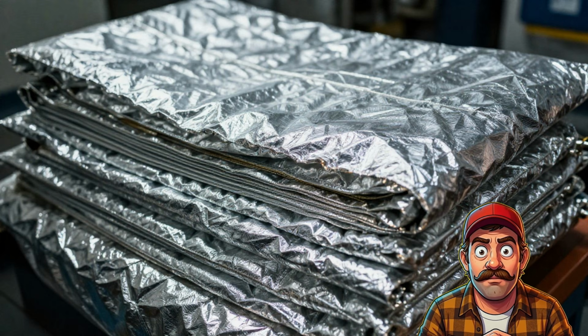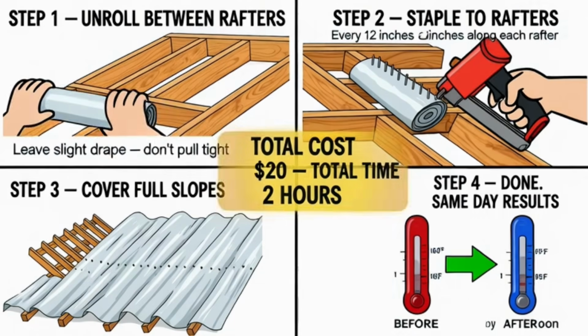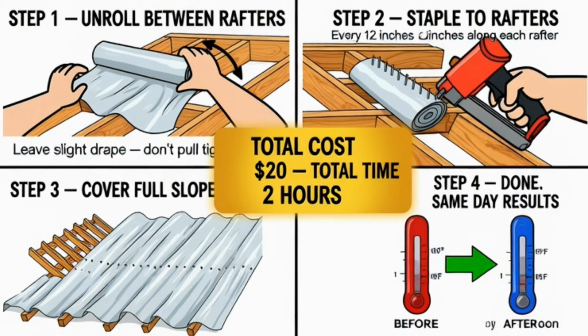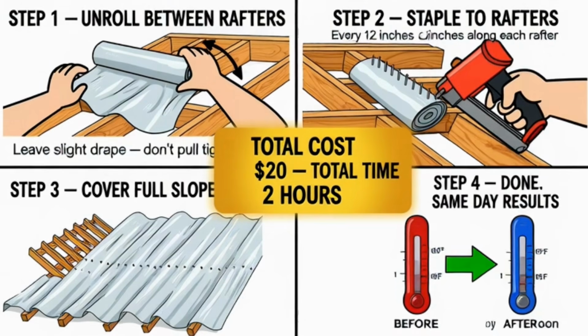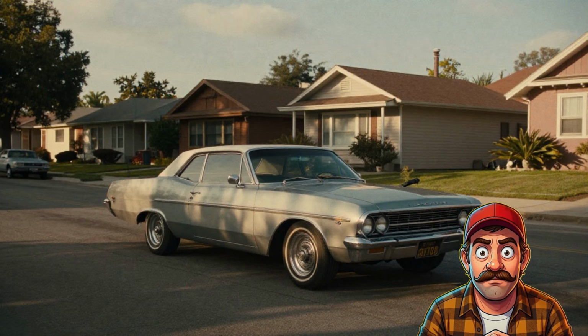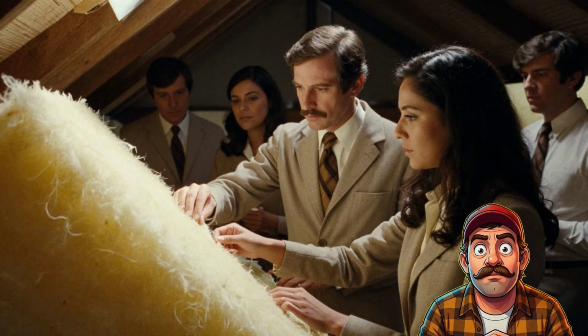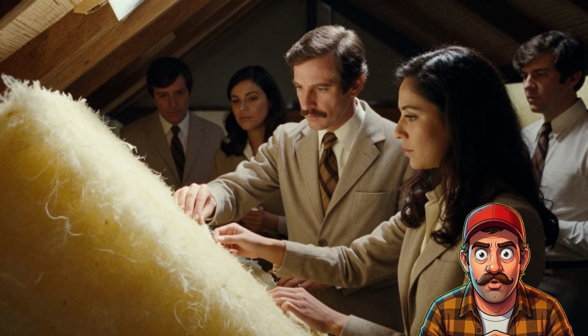Here is what a radiant barrier actually is. Aluminum foil. Technically, a sheet of polyethylene or woven material with a bonded layer of aluminum on one or both sides. The aluminum reflects radiant infrared energy instead of absorbing it. A properly installed radiant barrier reflects 97% of the radiant heat hitting its surface. The roof deck above it can be running at 170 degrees. The air on the other side of the barrier stays cool because the radiant energy never crosses.